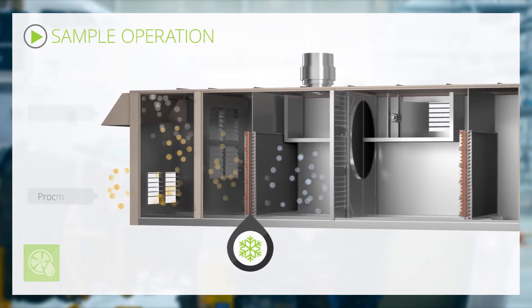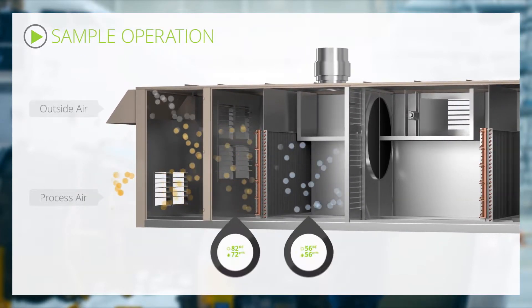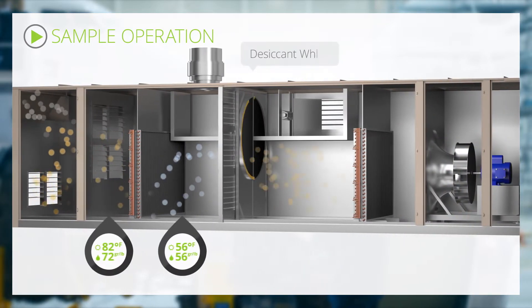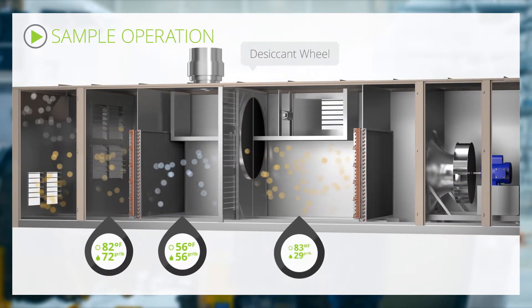In this example, humid process air is pre-cooled and partially dehumidified through the first coil. The cooled, saturated air then enters the desiccant wheel, which behaves as a dry sponge absorbing moisture.